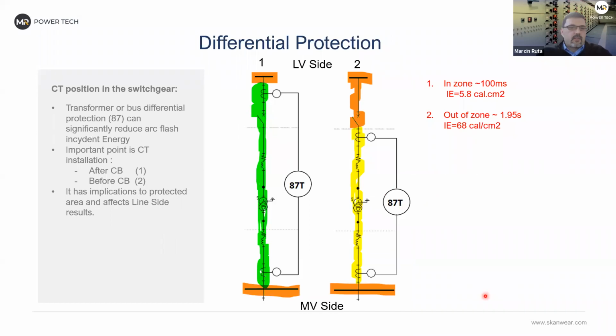What we very often see in the data center projects, which at least we will see, is the transformer differential protection or the bus differential protection. And this protection can improve the situation a lot. And a very important point to mention here, because it makes a big difference, is how we install the CTs.